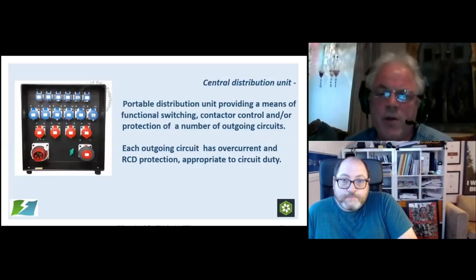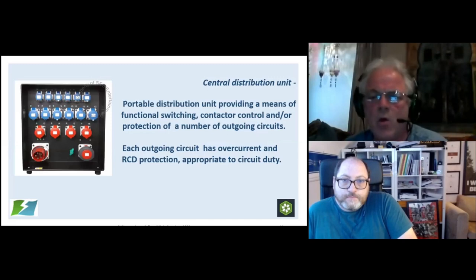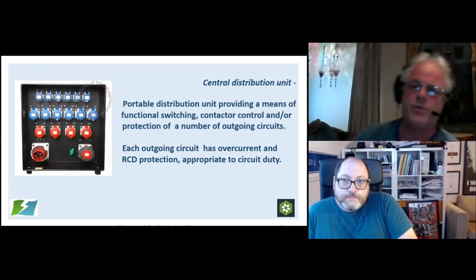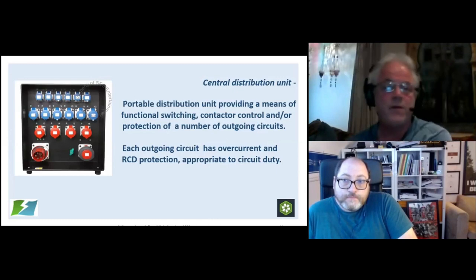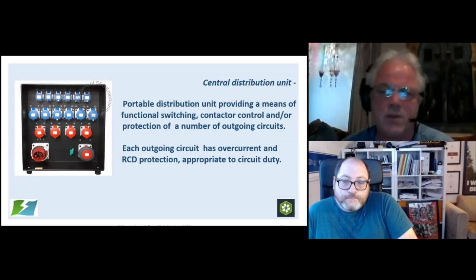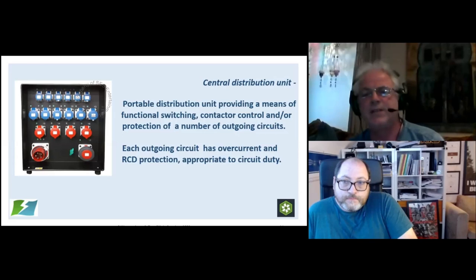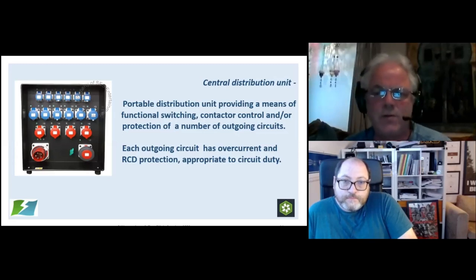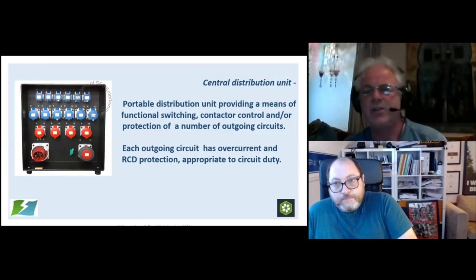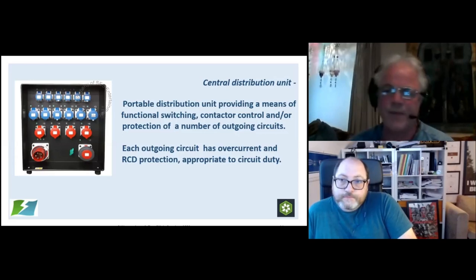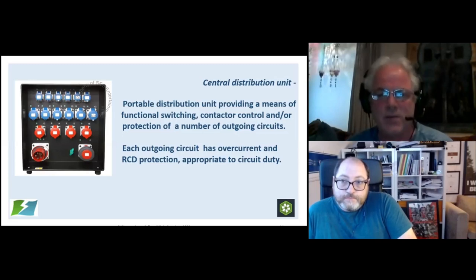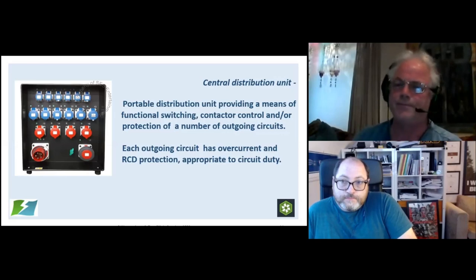The central distribution unit, these are slightly smaller units, and commonly can be used towards the center of loads, and they can provide supplies to final distribution units, and they also can supply final circuits. So they'll have a range of different types and sizes of sockets. Again, they must have the RCD protection which is appropriate to their duty. If it's a final circuit, it must be 30 milliamp RCD instantaneous. If it's a distribution circuit, again, adjustable selectable RCD with a time delay on it. These all need to be set properly so we get proper discrimination, or selectivity, as we're now supposed to call it under 7671.